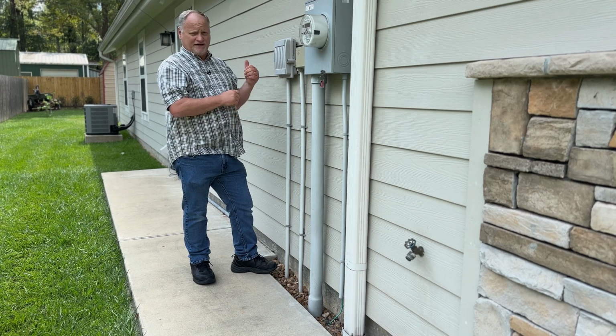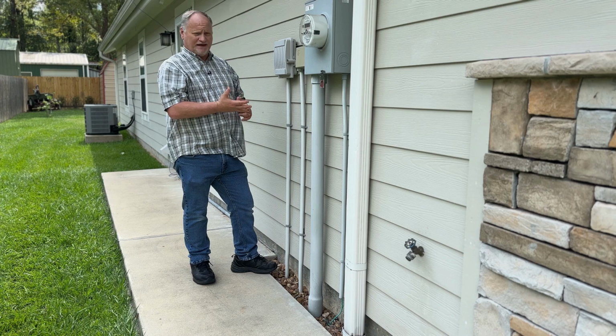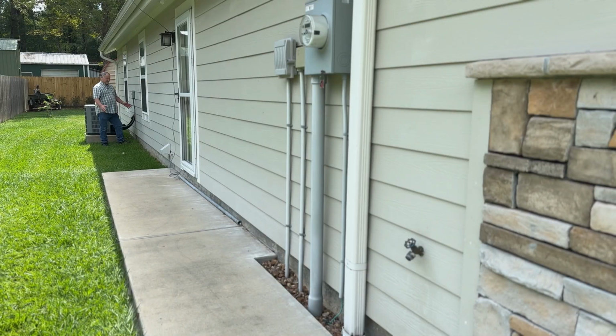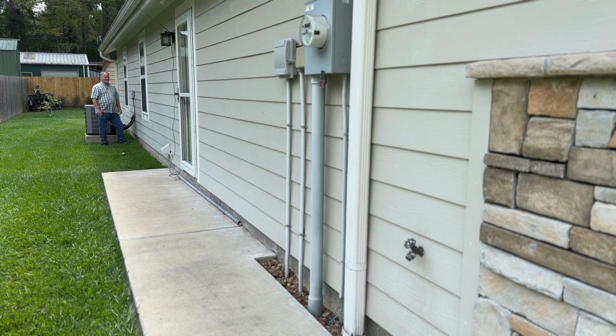So your data room, your data closet, your home lab should all be tied into the same ground. Now you may be thinking, hey, wait a minute, my data room is right behind this wall right here. So why don't I drive a ground rod here, go in through the wall, tie it into my little rack, and I'm good, right? Not so fast. You do something like this, you're asking for trouble. Let's go take a look.